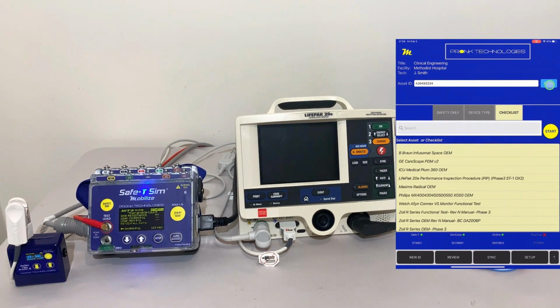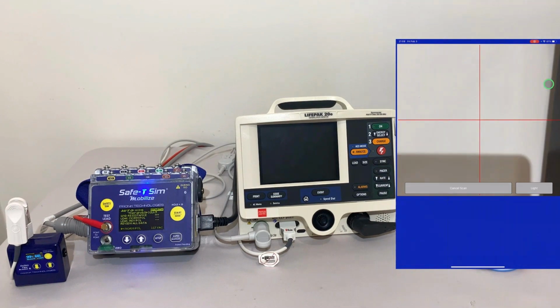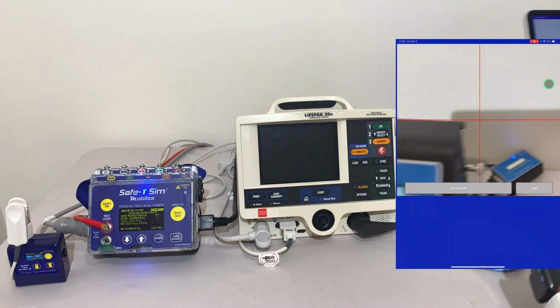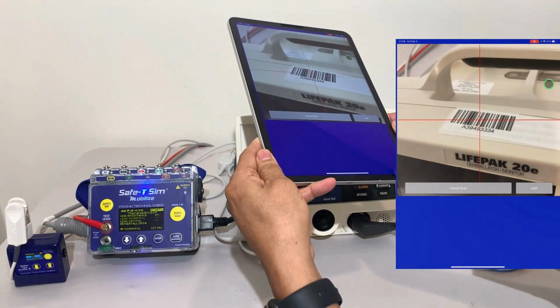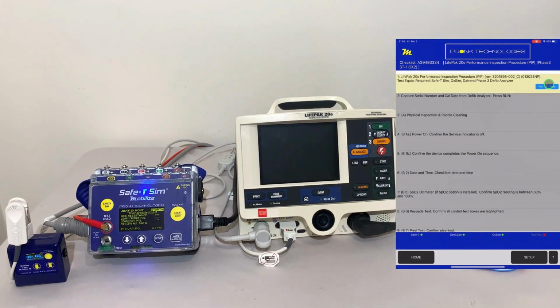If you have barcodes on your medical devices, the best thing to do is tap on the scan function. It will turn on the camera of your smart device, and I can go up to the barcode, scan it, and it will automatically open up the procedure that corresponds to this LifePak. Here you can see I'm now viewing and able to run the manufacturer's procedure I need to perform, the PM I need to do on this device. At the top, it gives you a little bit of demographic information about what test procedure we're going to run: the revision level of the service manual it is based upon, and the test equipment needed to run this procedure.